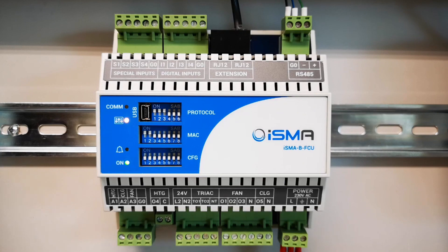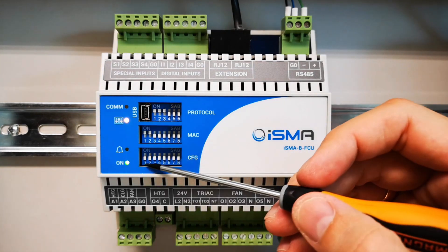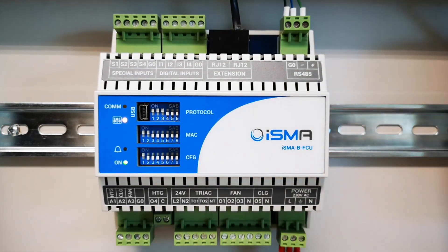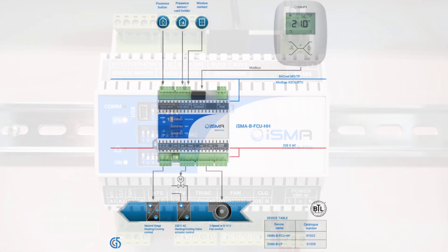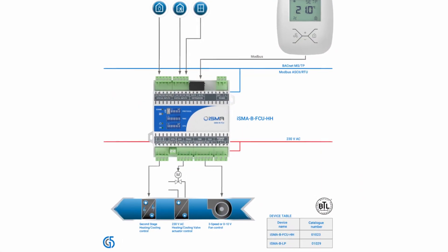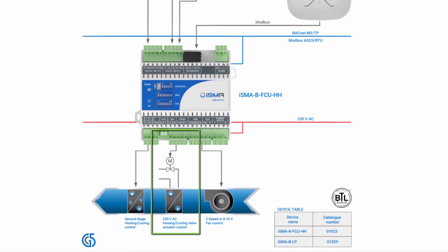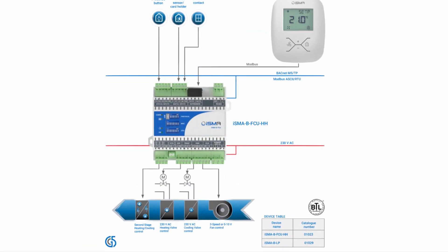The first DIP switch selects the fan coil unit type between a 2-pipe and 4-pipe water system. In case of 2-pipe, a single supply of water is available at the FCU — this may be either hot or cold water depending on the season.